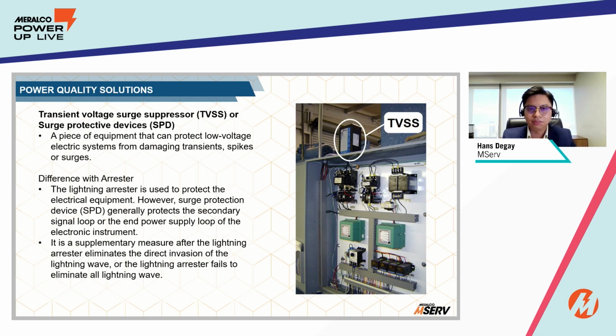The next slide is for TVSS and SPD: the transient voltage surge suppressor, or SPD for surge protective device. Actually, the term TVSS tends to be more popular in countries that adhere to the UL standard. Although TVSS always belonged to a larger group of surge protection, beginning in the 2008 NEC, the term SPD formally replaced the labels for both TVSS and secondary surge arresters. So there is a difference with the lightning arrestor that we commonly see, because an SPD is designed to protect the low voltage electric system from damaging transients. It is a supplementary measure in case the arrester fails to eliminate all of the lightning wave.